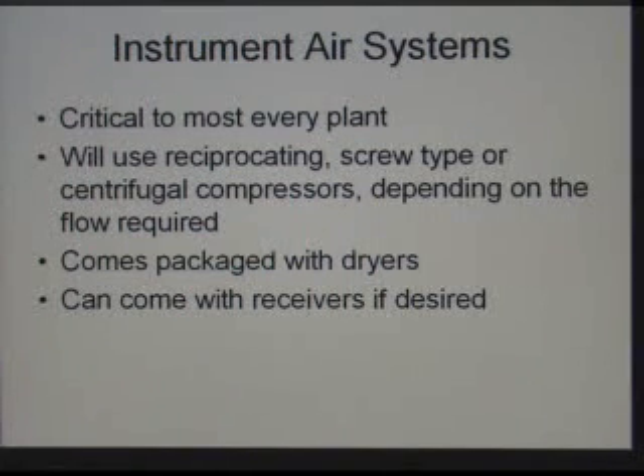Air is wet, it has humidity, and instrument air systems generally want extremely dry air, especially if you're in regions which get below freezing temperature. If you have water in your air system, it'll eventually work its way to a low point and sit. But if it freezes, it acts as a blockage, and now your air system won't be supplying air to the downstream users. So what you have to do is dry the air to a dew point below whatever your local ambient minimum might be. So for Alaska, with a minimum of -40 or -50 Fahrenheit, we would always have our instrument air spec'd out to be -60 to -100 degree Fahrenheit dew point. That avoids any complications of having ice formation in instrument air systems.